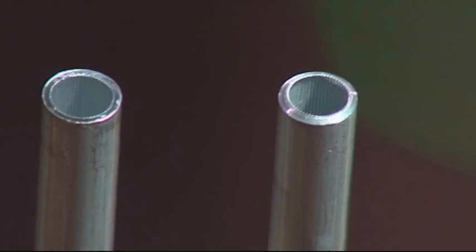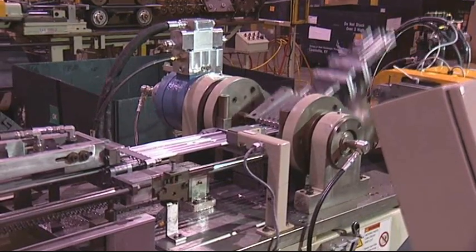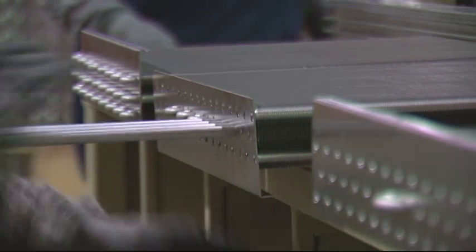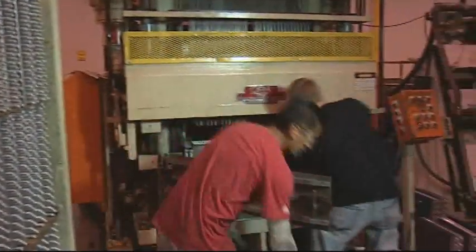The whole process starts with a hairpin. This is where quality starts — we've got to make sure that this hairpin is even on the end so that we can expand it and the ends come out right with the right flare. We're also critical on the overall measurements here. Operators check that hourly to make sure we're not building unusable hairpins. The hairpin benders are retrofitted with a stretch straightener, which helps make the tube even straighter so we can place the aluminum tube into the aluminum fin. The tube is also pre-lubed to help expand it over the expander.